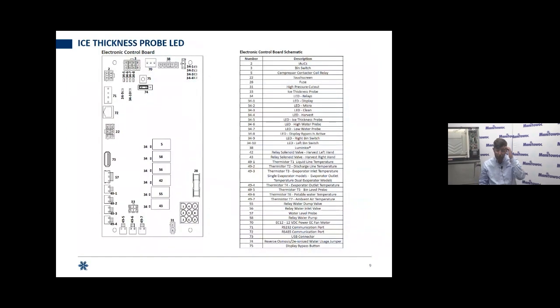All right, the ice thickness probe LED. This one is one that we get a lot of questions about. So on previous versions of Manitowoc ice machines, so the S model, the Q, the J, and the B model, they all used a water sensing ice thickness control probe. So we were not sensing ice, we were sensing the water going over that ice. So anytime water would come in contact with that ice probe on those machines, it would flash. And as ice formed, and you had constant contact with that ice probe, that light would light up solid. That's not what we're doing here.